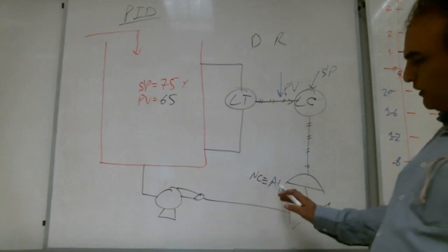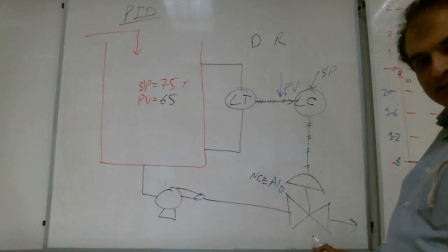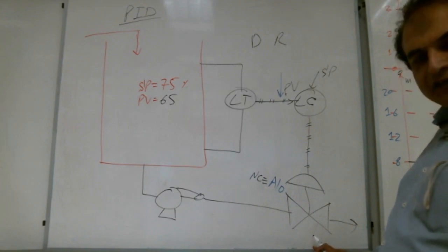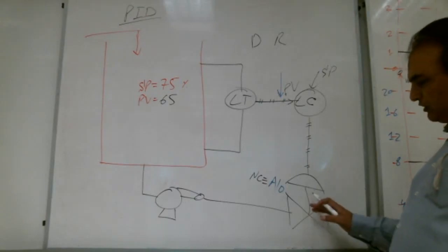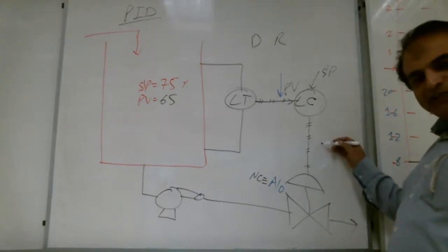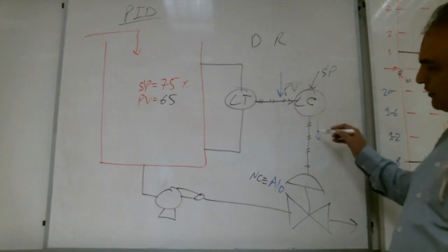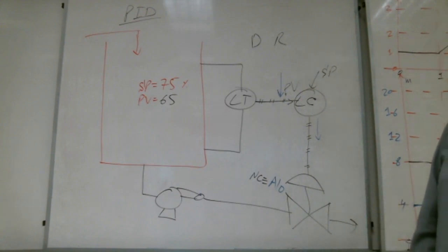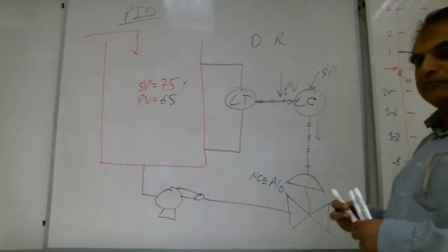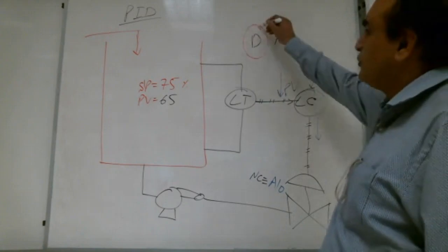It is a normally closed valve, air to open. If we remove the signal, it will get automatically closed, right? So we need to reduce the signal or increase the signal? Decrease the signal. Both arrowheads are down, right? If both arrowheads are down, is it direct or reverse? Direct. A lot of brothers are typing direct. So it is direct.